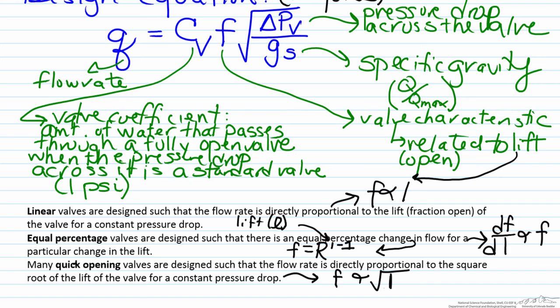Because of this rationale, quick opening valves are used for safety only and are not used for controlling systems. This setup of trying to have very high amounts of flow very quickly makes it very difficult to control at these very low openness values.